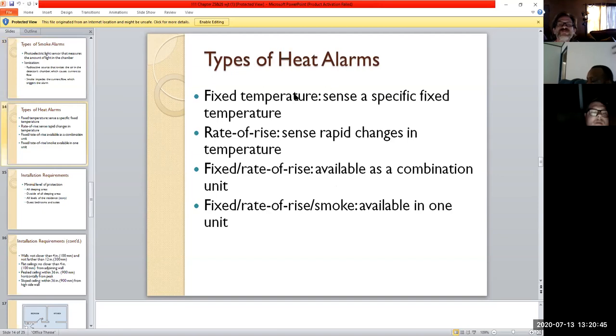Then we got the heat alarms, which sense a specific fixed temperature based on your normal operating range, and also notice rapid changes in temperature. So in a fire, where you go from say 75 degrees up to 100 or over, it'll immediately sense that big change. Slow changes, like going from 75 to 80 because you turned up the air conditioner, won't affect it. This looks more for a quick change in temperature within minutes.